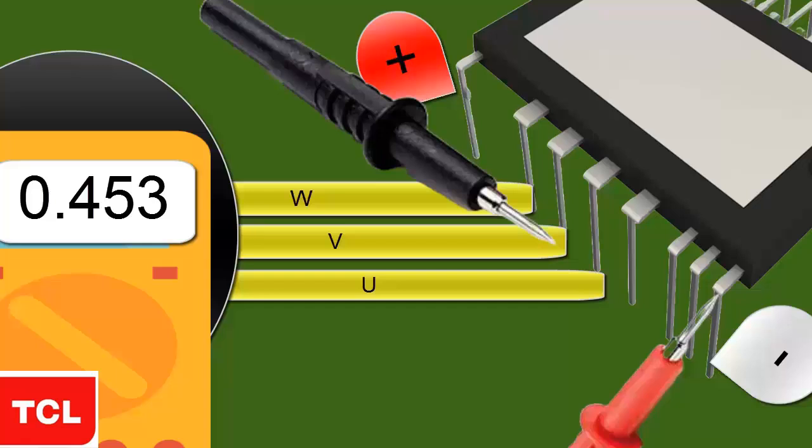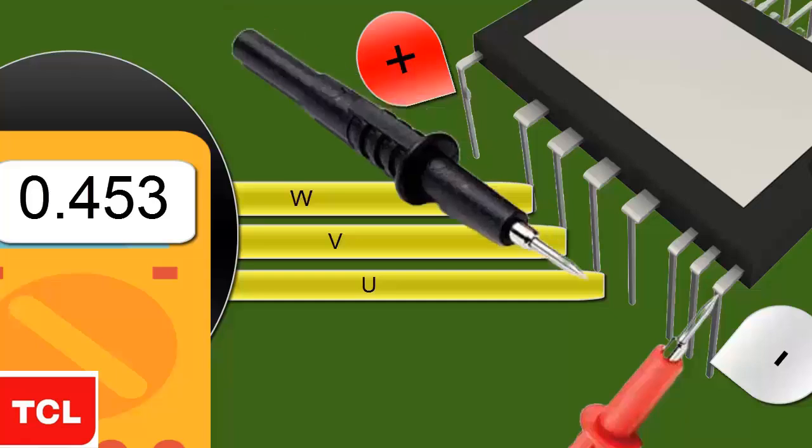The minimum voltage activation values should be similar to those obtained previously. The measurement obtained between the negative supply and each pin, UVW, should yield practically the same reading.